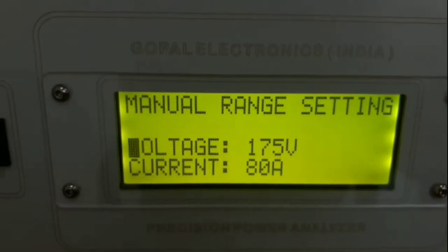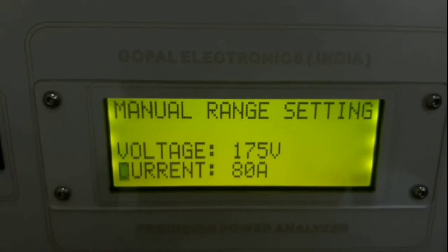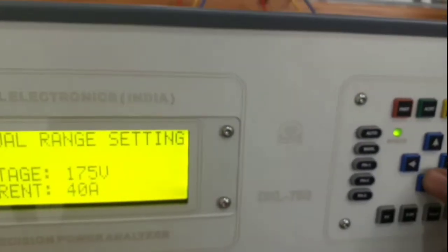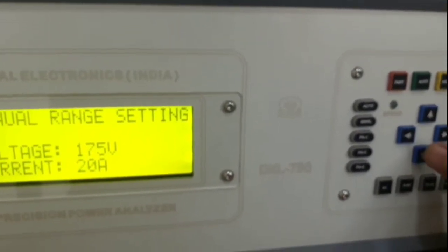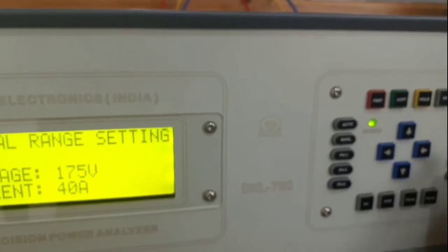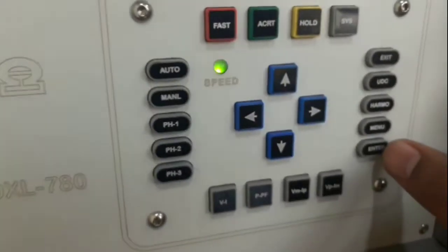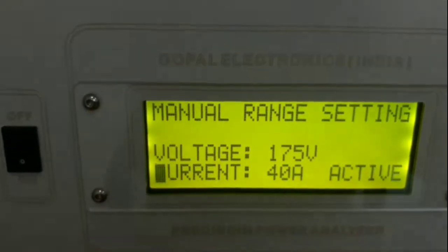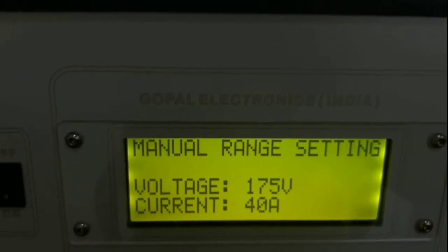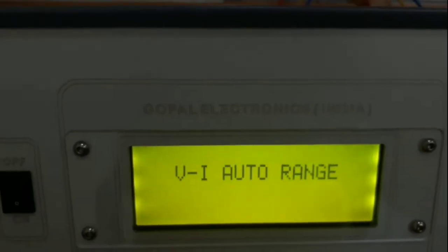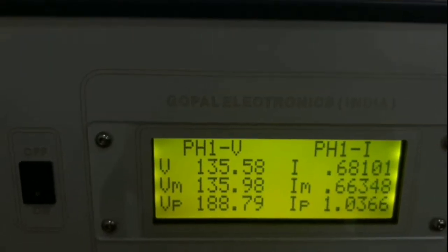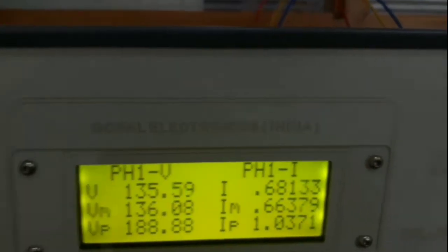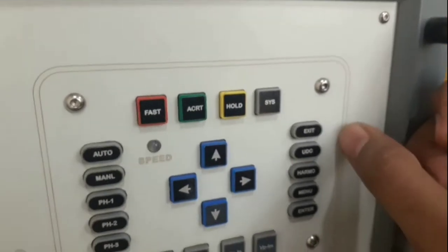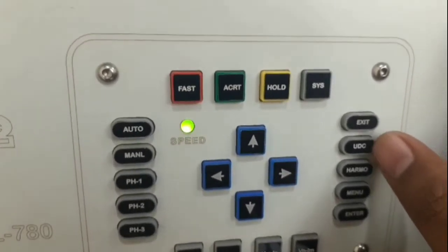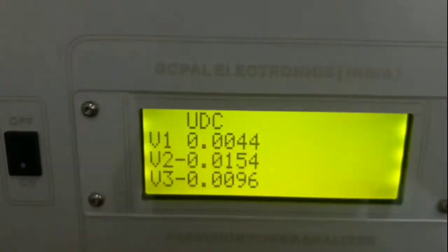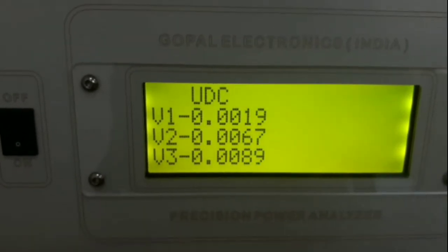Now if you want to change the current range, press the manual key, and by pressing the up down key, you can set the value. If you want to enter a 40 ampere range, then press enter. Now it will be activated. But for now, we are measuring in auto range selection mode. You can see that the UDC function is given here. By pressing this key, you can see the UDC value of all three phases.